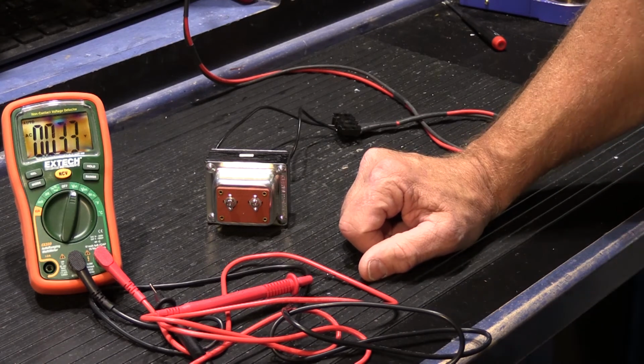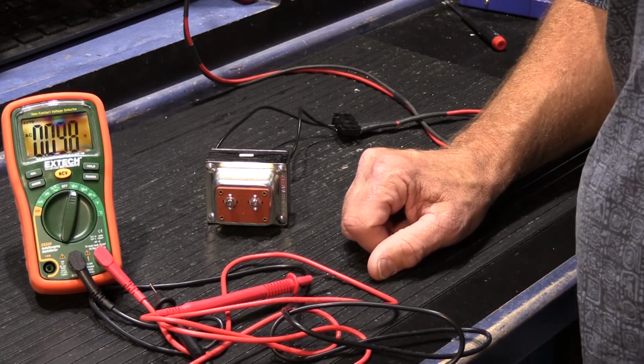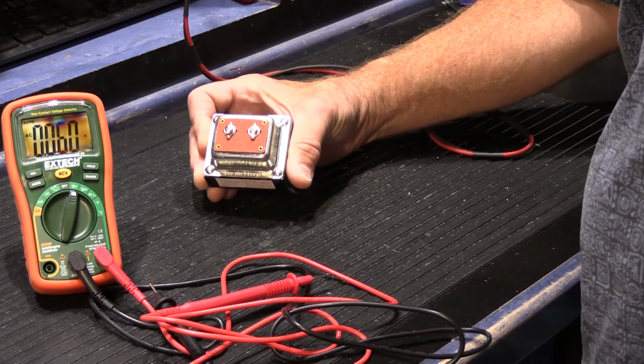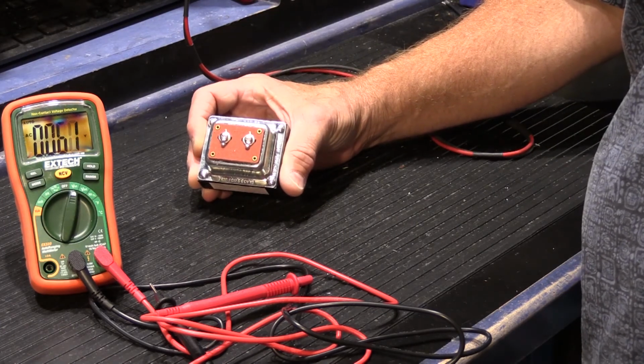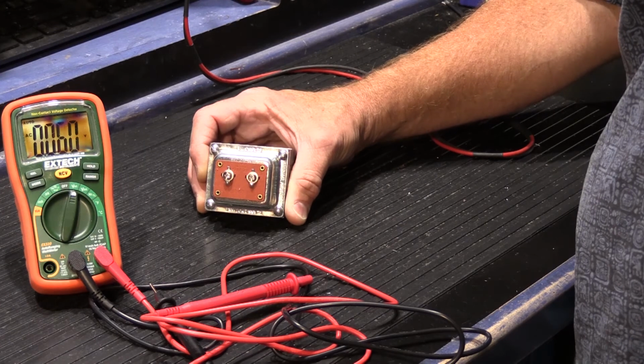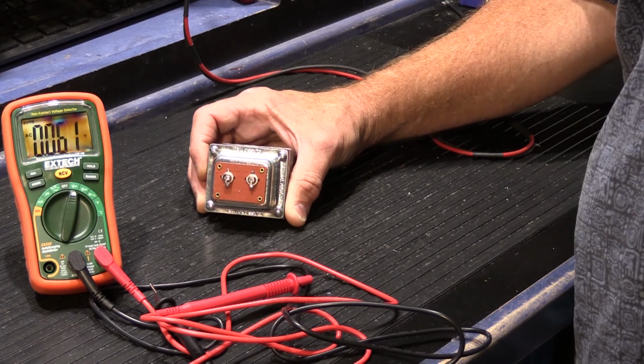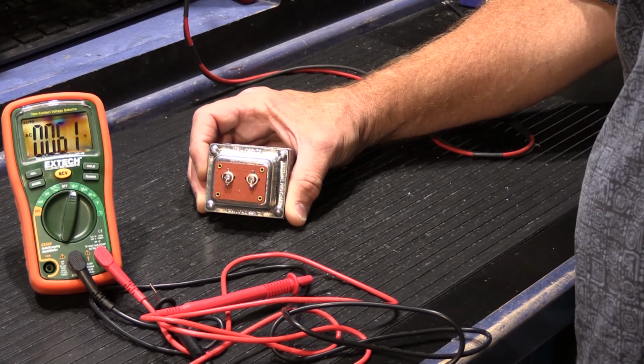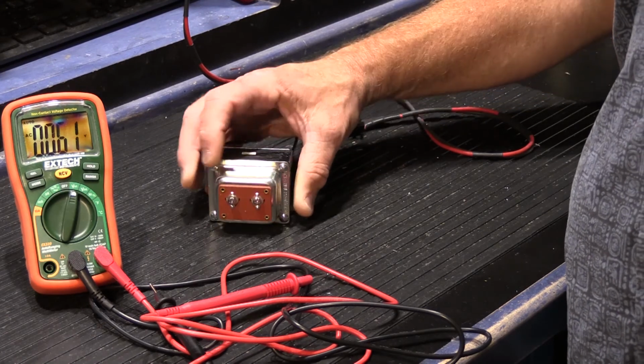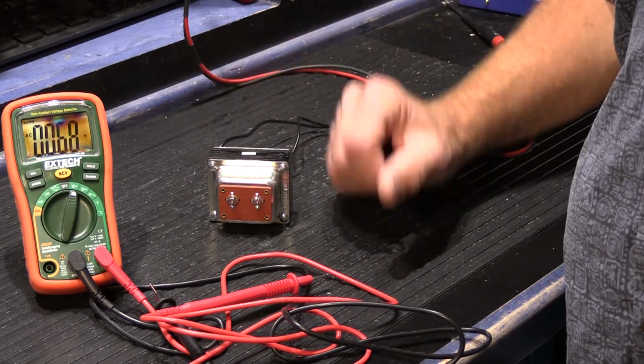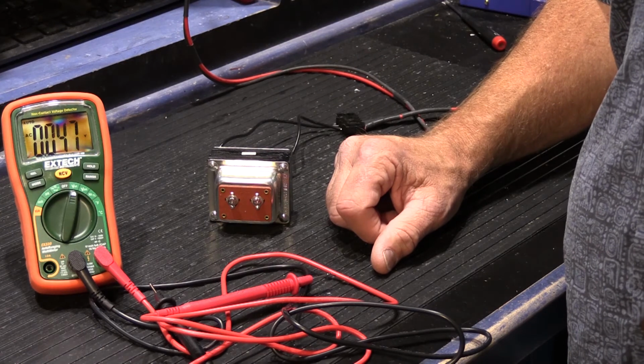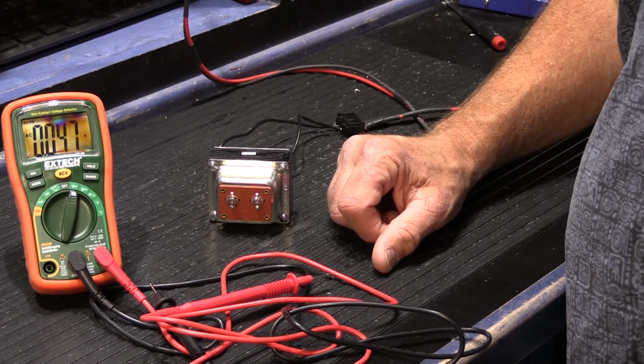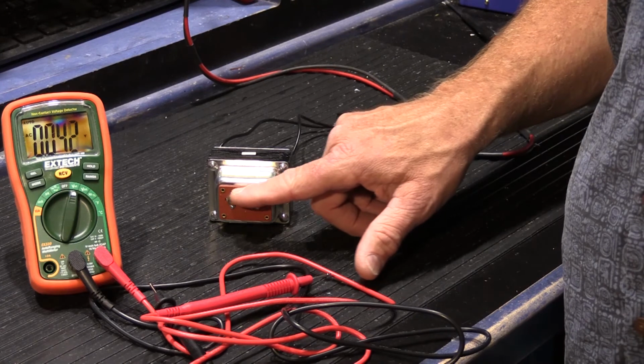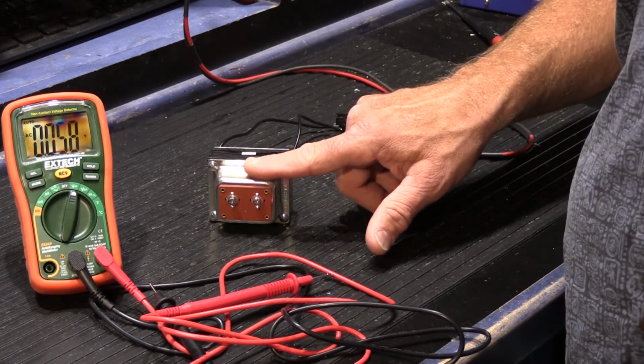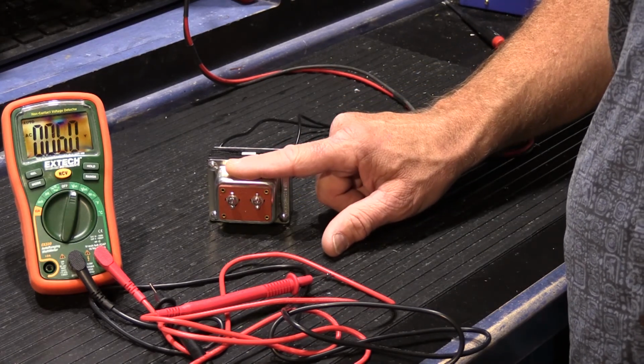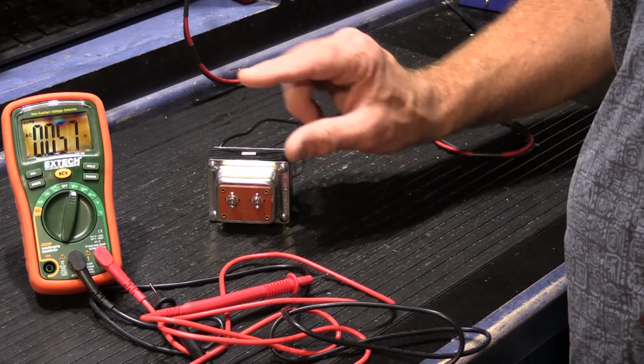Lastly, to give you a little bit of confidence so you'll sleep well after you watch this video, almost all modern NuTone transformers, transformers that have been made since, say, 1974 and later, all have inside of them a device called a thermal limiter. A thermal limiter is a heat sensing switch, and it's usually on the secondary side, on this half of the transformer, and it does exactly what it sounds like. It's a heat sensing switch.